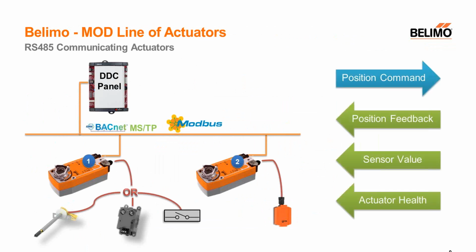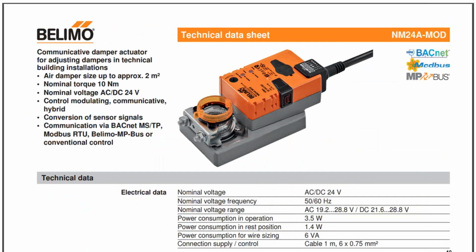Once you have these hooked up and communicating, you can now, from your DDC system, send a command to the actuator to tell it what position to go to, just like you'd do with a 2 to 10 volt signal. But then you also, basically for free, get feedback. Where's the actuator at? What's the value of the sensor that's attached to it? And then you also get indication of the actuator health, whether it's working well or not, if it's hit its torque limit, stroke times, things like that. This product is available today. Here's a quick look at the top of the cut sheet. If you want to see more about this particular actuator, just search for the Dash Mod on the Belimo US website, and you'll get a list of all the different damper actuator types that we have that support BACnet and Modbus.